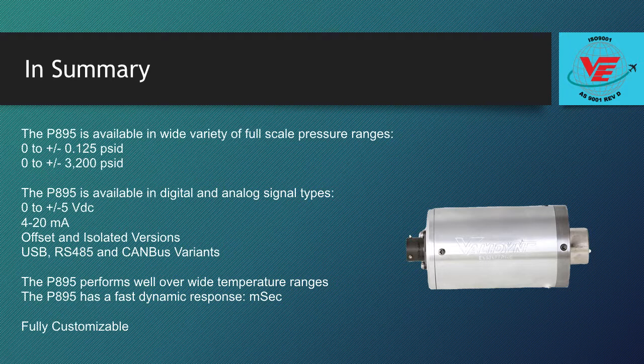The small sensor cavity allows the P895 to have very fast response times, making it suitable for dynamic pressure measurement. Because of the modular nature of the design, the P895 can be customized from the pressure ports to the connector. The pressure calibration can be done in any units of pressure as well as custom temperature ranges.